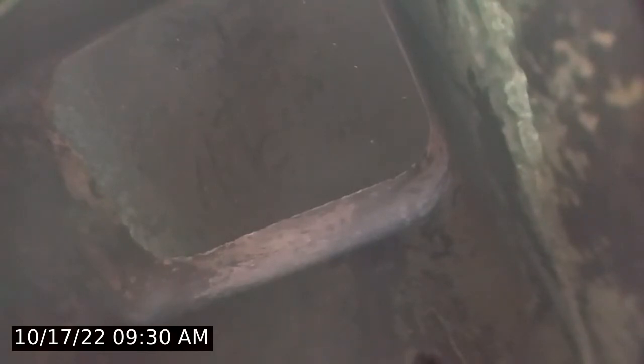We are video inspecting the porch fireplace, or sunroom fireplace, whatever you'd like to call it. It is a 1318 flue, and we had a PCR performed to this flue. We were not able to coat it with the plug, so we sprayed it from the top down and the bottom up due to the flagstone being installed on top.